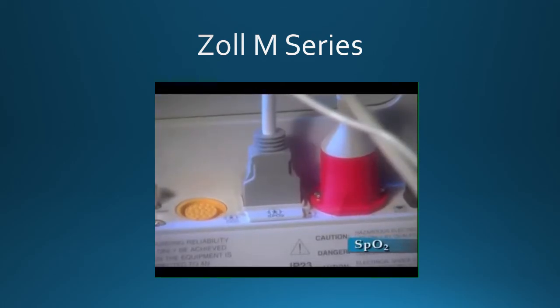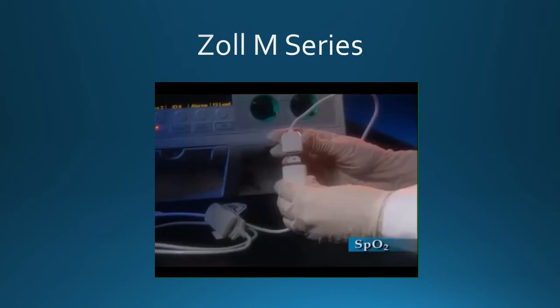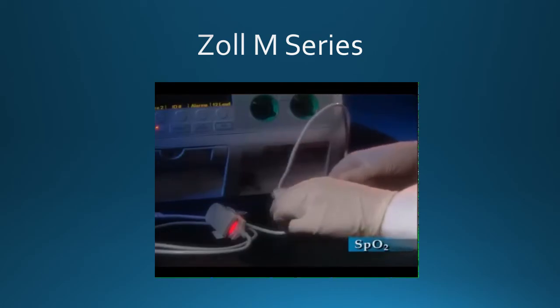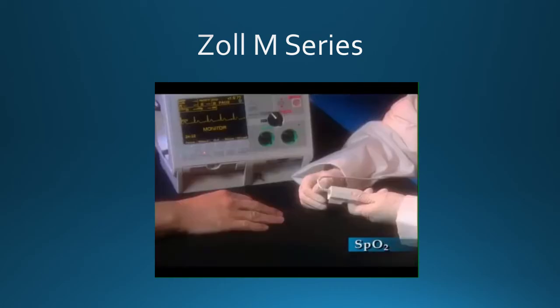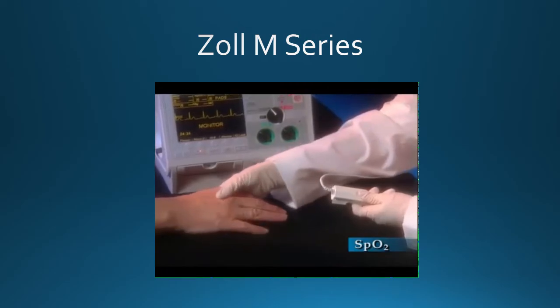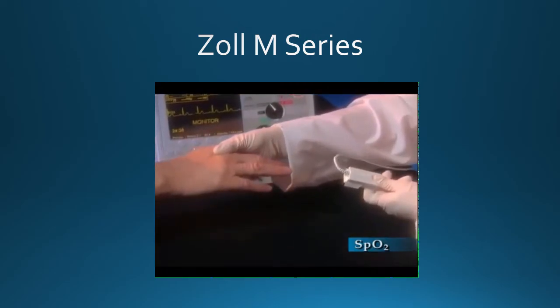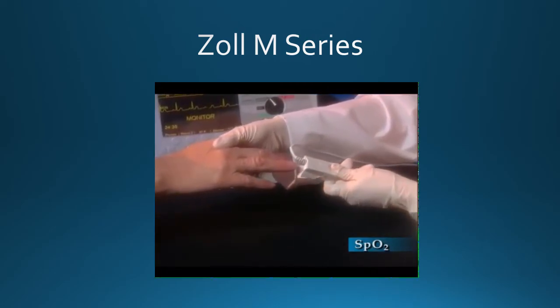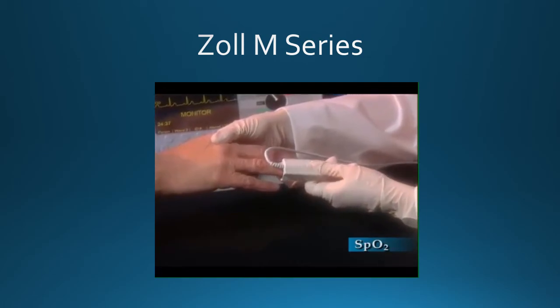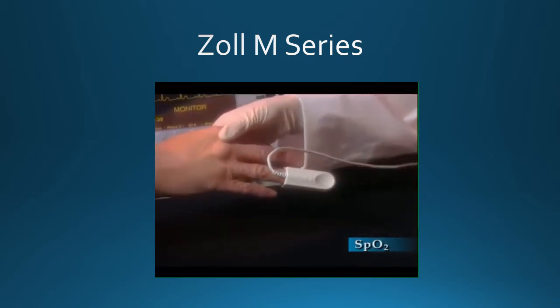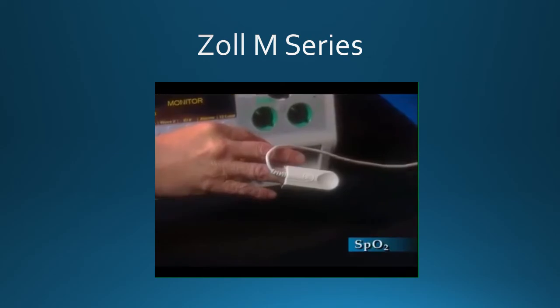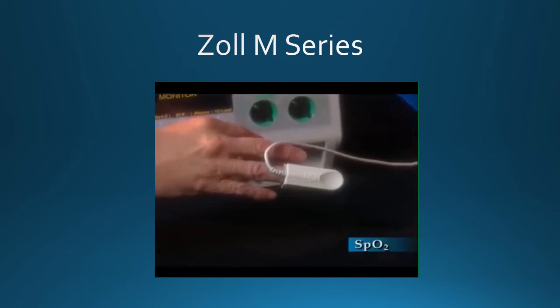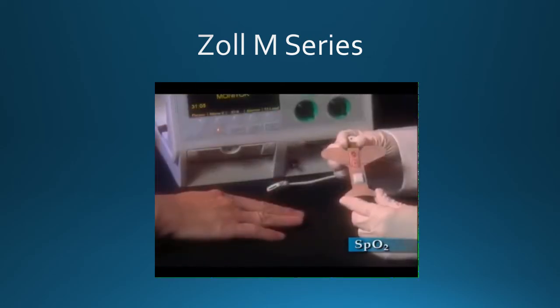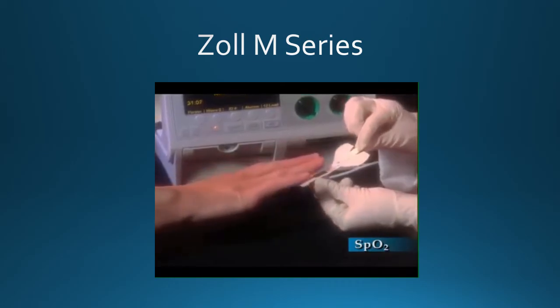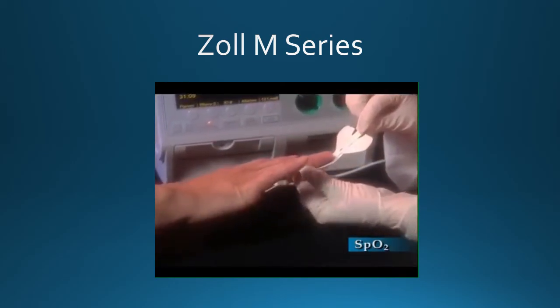of the M-Series. Plug the sensor into the SPO2 patient cable. The reusable sensor is simply placed over the appropriate site. Attach the sensor to the patient. Choose a site that is well perfused and one that is least likely to restrict patient movements. The ring finger or middle finger of the non-dominant hand is preferred. The disposable sensor should be placed by carefully following the instructions on the package.